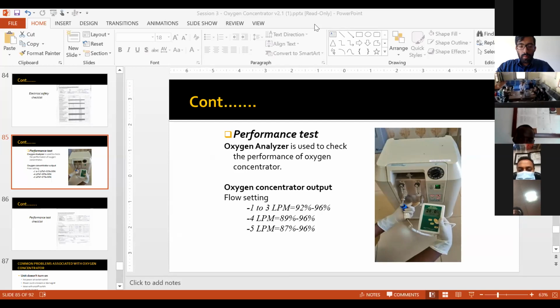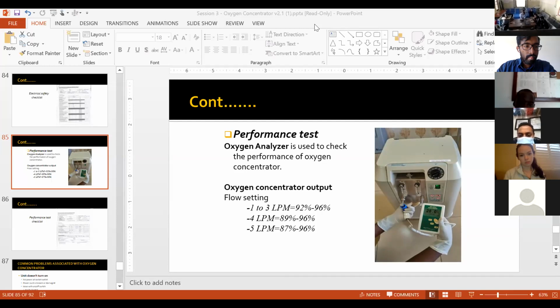So as the flow increases, the oxygen purity can reduce as well, because you are pushing too much air into the system. What happens is, when there is too much air, the sieve bed tank starts to work more, and the purity can reduce a bit. That's all. But as long as it is inside the range, that's a great result. So basically, you should be in that particular range.